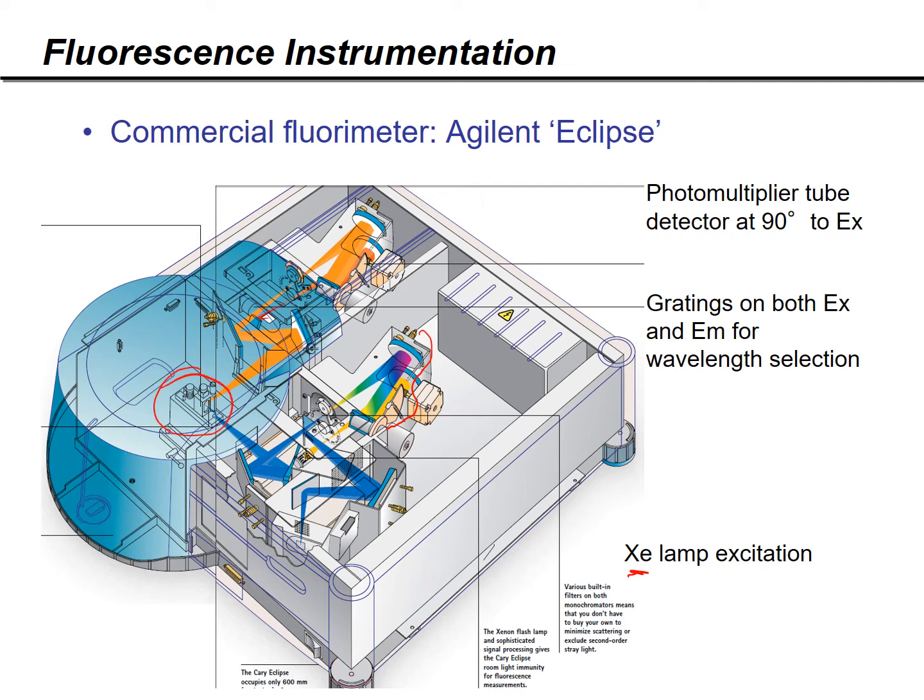There's the sample in there, and the fluorescence is shown by the orange line. So they're keeping the right color arrangement there. Orange light is lower energy than blue light, so that's recognizing that there is a Stokes shift. And if you wanted to measure a different wavelength, then you can scan the monochromator with the grating in it on the emission side. That's how you get that whole spectrum, by scanning through those emission wavelengths.